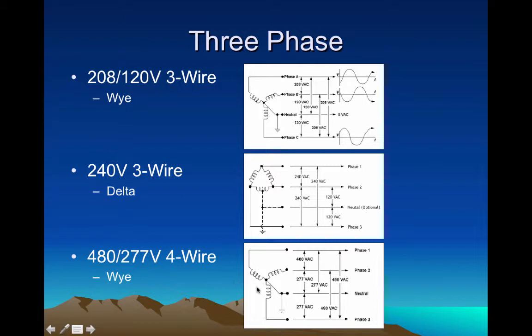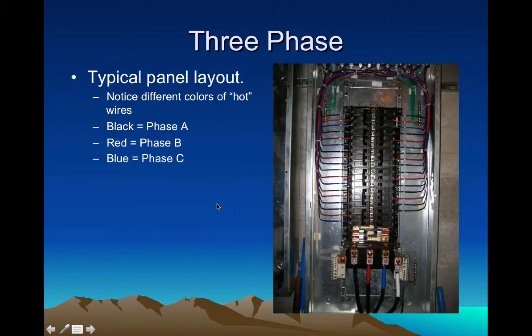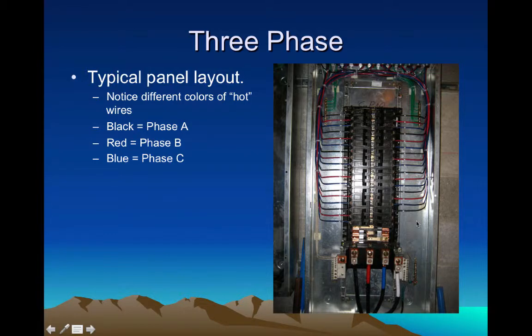When you look at the inside of a three-phase circuit breaker panel, it's important to note how the circuit breakers are laid out. Even if everything is covered up, you have three different phases — black, red, and blue — with the black, red, and blue wires tied to different circuit breakers. All blacks are on the same phase, all reds on the same phase, and all blues on the same phase. In a three-phase panel, each phase is one of three, so they go in groups of three — first phase, second phase, third phase, repeating. Every third circuit breaker is going to be on the same phase.